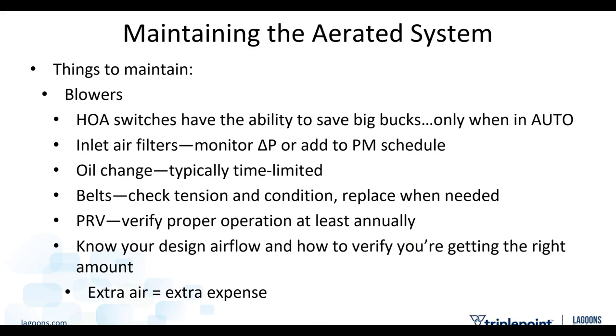So an aerated system, you're going to have a lot more to do with an aerated system. First of all, you've got blowers. Blowers, a lot of times, have hand-off-auto switches, and you have the ability to save a lot of money. There's a lot of engineering and thought that went into that hand-off-auto switch. Not so much the switch, more so the sequence of operation, the ladder logic, everything that's in the PLC behind it. But it only does you a benefit when it's in auto.